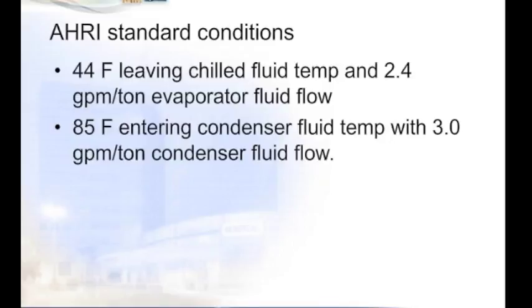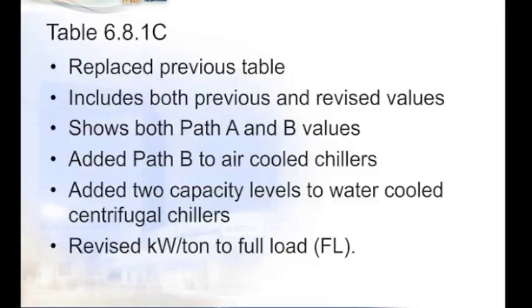One of the features of the standard 90.1 is Table 6.8.1C. It's been there for a couple of versions. And what's different about this one? Well, the addendum CH has included a new table that completely replaced the old one. But now it also includes both previous and new values, previous to the requirements of January 1st, 2015, as well as the new versions.